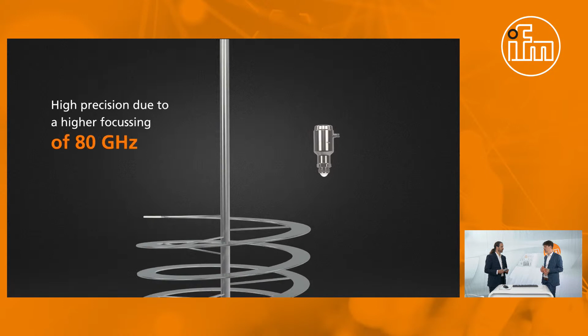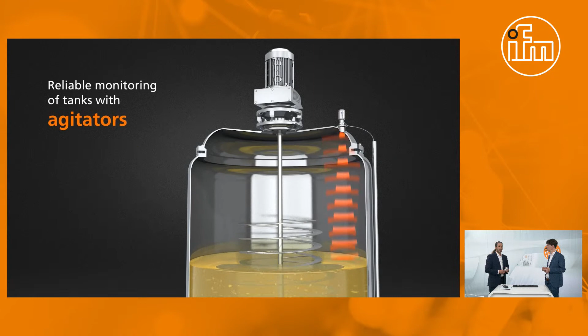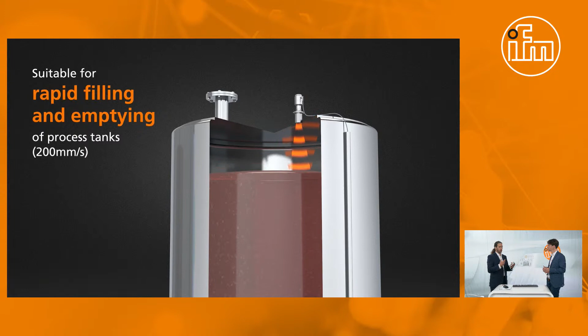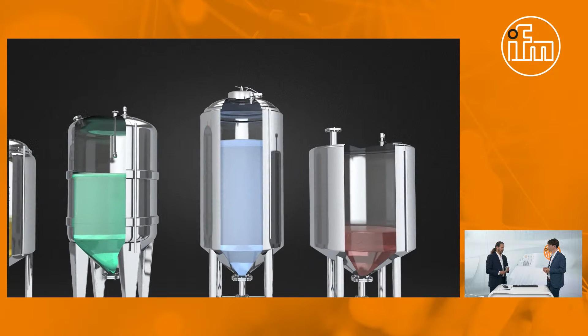Level measurement is actually not that easy as it typically seems. We typically have harsh environments, different and difficult applications, and that starts, for example, in food industries with internal constructions within tanks. It happens very often that products need to be stirred, and to stir the product within the tank, there are agitators installed. As you can imagine, when you have a technology that has contact with the medium, like our guided wave radar, or even non-flush pressure sensors, this could be a disturbance for the measurement, or not even possible.